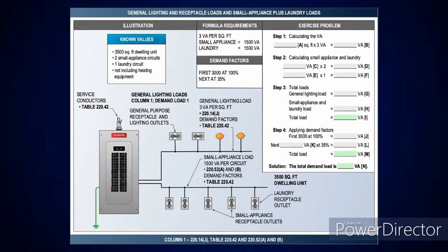Okay? And this one here, we tell you we got a 3,500 square foot dwelling unit. We've got 2 small appliance branch circuits and 1 laundry circuit. I've already set it up for you, and you total it all up and get what your total demand is. Just remember the first 3,000 VA is taken at 100%.